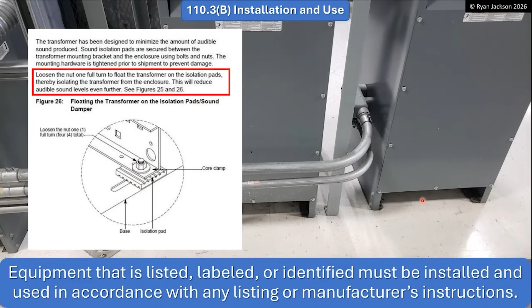This is a question that gets brought up all the time: what about transformers? Can you run non-flexible conduit to transformers, or do you have to run flex to them? No, you can run solid conduit to them all day long. I've seen hundreds of transformers with solid non-flexible raceways going to them. If you do industrial or big heavy commercial work, where there's moving equipment and things subject to damage, you're not going to have flex going to these things - it's going to be hard pipe.